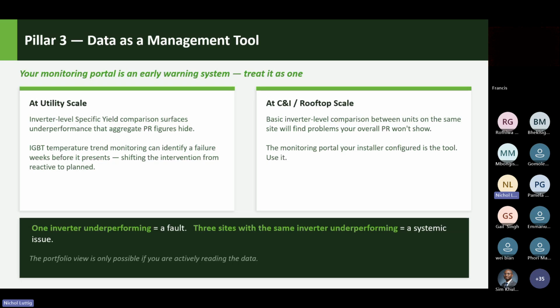And then really good examples on the left side, and I'm currently sitting with a similar situation that we had recently. So the IGBT temperature example is instructive. If you are tracking thermal trend on your inverter power electronics, and you see a gradual upward drift over weeks, that is a failing cooling system announcing itself. And the 2 or 3 other parameters that you can look at can quickly tell you what around the cooling system or ventilation actually becomes the problem. So then you can plan the intervention before it becomes a forced outage.